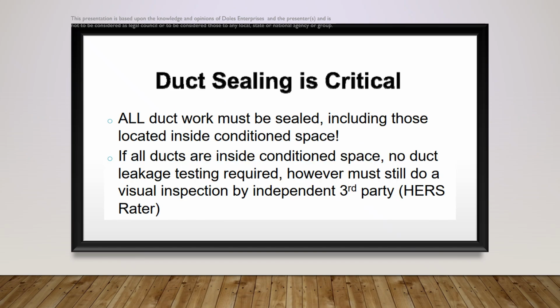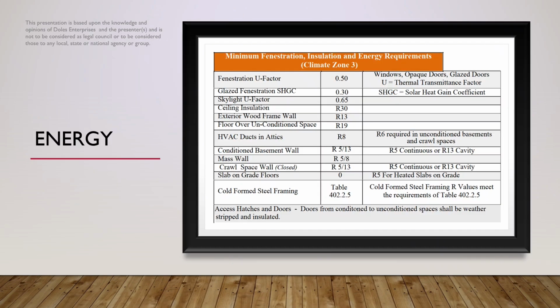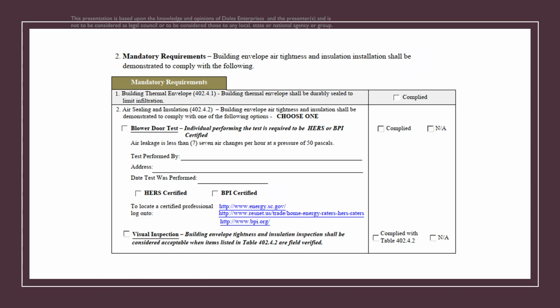All ductwork must be sealed, including those located inside conditioned space. If all ducts are inside conditioned space, no duct leakage testing is required. However, they must still do a visual inspection by an independent third party, HERS Rater certified. We encourage you to reference the code requirements for the climate zone relative to your jurisdiction. For our example, we're using Climate Zone 3. Duct tightness and visual inspection compliance certifications must be available for the inspector.